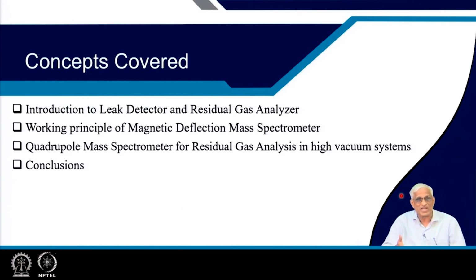So, the same residual gas analyzer which is going to tell the problem in the system can be a useful tool to know the chemistry of the residual gas. In the initial days of vacuum technology, these things were designed to solve the problem of getting better and better vacuum. Now, these things are taken in a different shape. For example, partial pressure measurement.